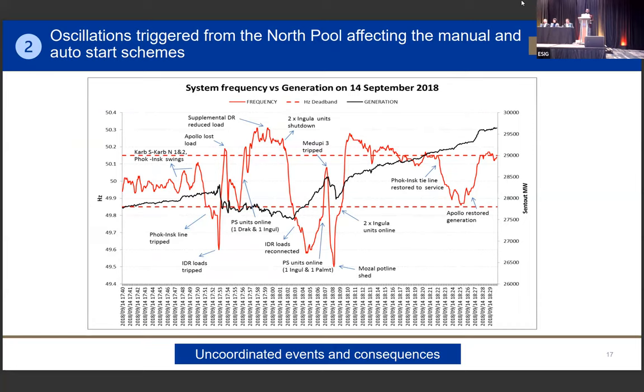So there was load that was lost. There were some units that tripped. So we're going up and down, frequency going up and down. Then also there was some manual intervention. The controller will call one of the portions in to synchronize. And then it was late. And the next thing is frequency is high. So there were a lot of uncoordinated events. But after this incident, we coordinated and made sure that we balance between the auto responses.